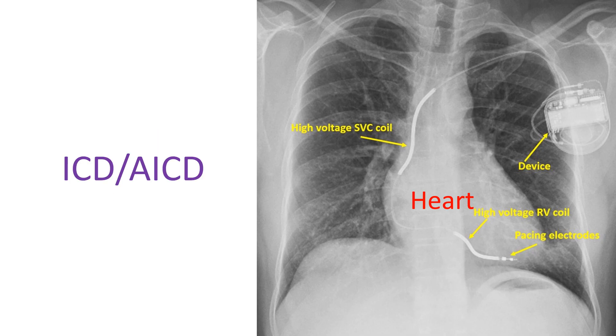The defibrillator has a capacitor which can store energy at high voltage. When a serious rhythm disorder requiring a shock is detected, the device charges automatically and delivers the shock within the heart. The current passes from the high voltage coil to the metallic can of the device.